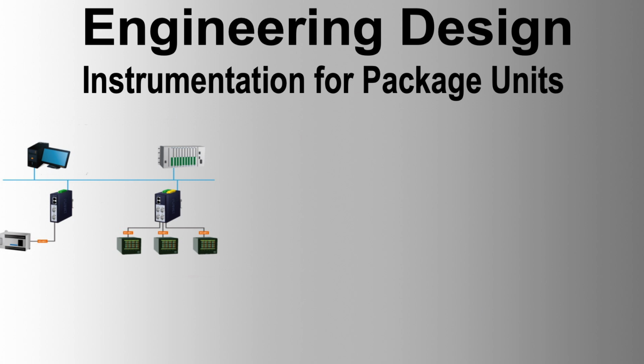The equipment package control system shall communicate with the plant DCS or SCADA for indications and alarms as described in the following section. IPF. A PLC-based IPS logic solver should be applied and may also be used for solid-state or magnetic core IPSs, logic solvers.